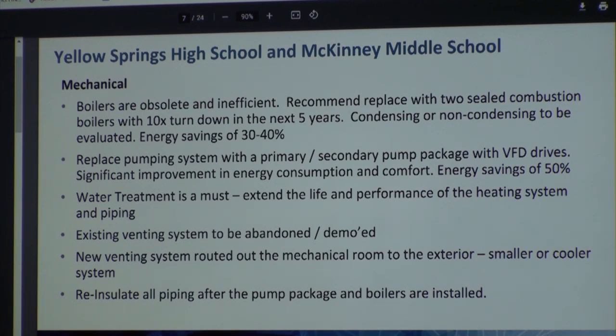Do the louvers work? I don't think they work anymore, I couldn't get them to. So that means it's sucking air out of the building into the basement, you're heating the air, distributing it through the building, then sucking it back out and putting it through the boiler. If you do the math on how much air goes through that boiler, it's a lot, and I don't know how it's controlled. We kind of got an idea by looking at the controls, but is it that you need two on a cold day and the third is redundant?